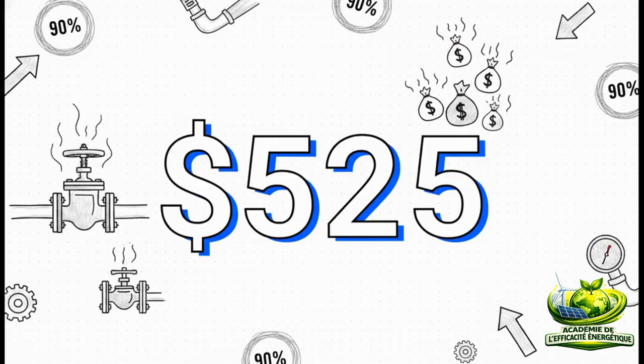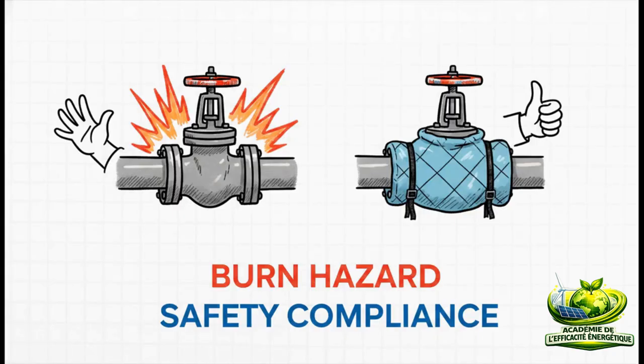Ignoring this is an incredibly expensive oversight. Think about this. Just one single uninsulated 6-inch gate valve running at 305 degrees Fahrenheit is costing you $525 every single year in wasted fuel. Just one. Imagine walking through your facility right now. How many bare valves, flanges, and steam traps do you think you'd find? According to the Department of Energy, throwing some proper insulation on those can reduce those specific energy losses by a whopping 90%.